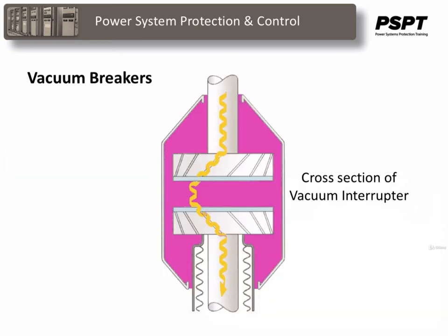The main aim of this circuit breaker is to quench the arc when the AC current cycle is at zero or zero crossing, and by establishing a high dielectric strength in between the contacts so that reestablishment of the arc after the current reaches zero becomes impossible. The dielectric strength of a vacuum is 8 times greater than that of air and 4 times greater than that of SF6 gas. This high dielectric strength makes it possible to quench a vacuum arc within a very small contact gap. For short contact gaps, low contact mass, and no compression of the medium around the contact, the drive energy required in a vacuum breaker is at a minimum.